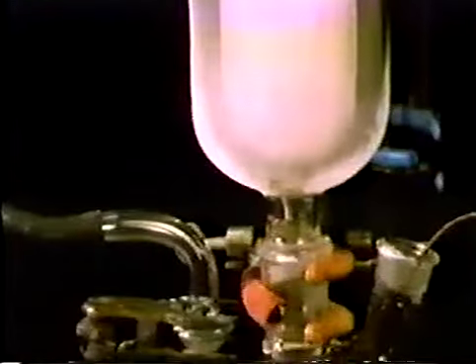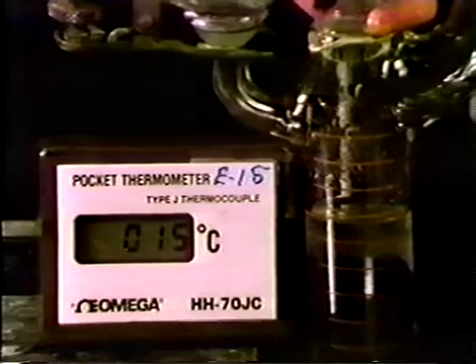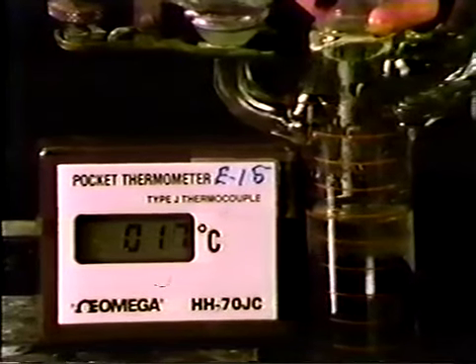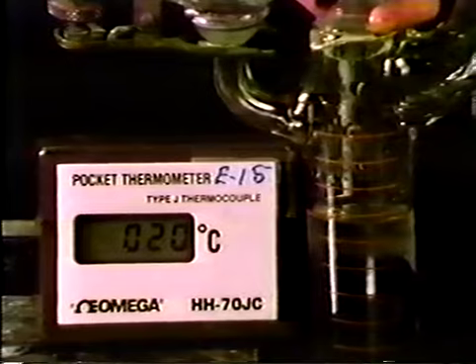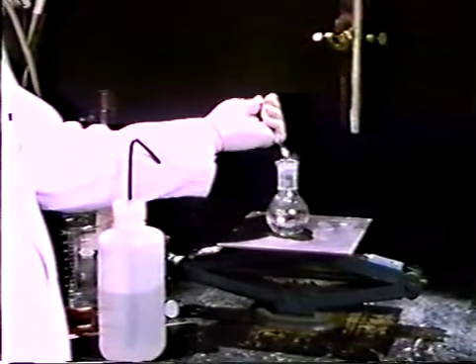Ammonia is not reactive with water and, in fact, is highly soluble in water. However, there are some attendant hazards. Anhydrous ammonia liquid has a high heat of solution in water. If water is poured onto a pool of liquid anhydrous ammonia, the product will boil vigorously, increasing vapor release.